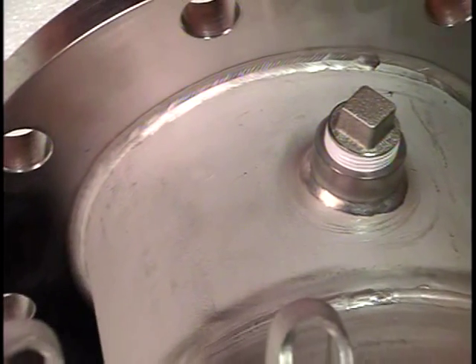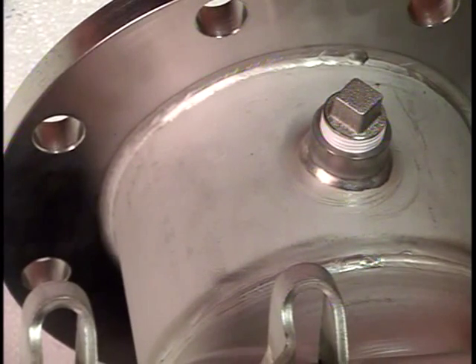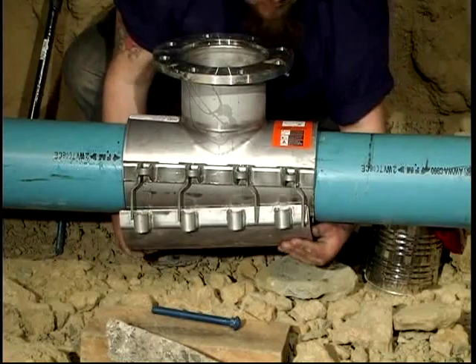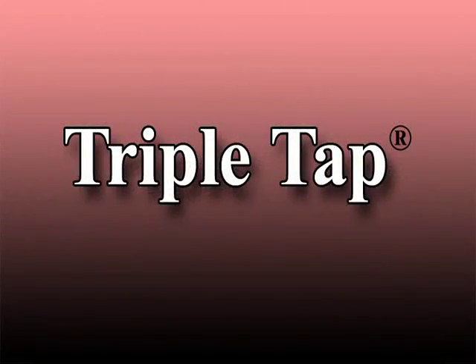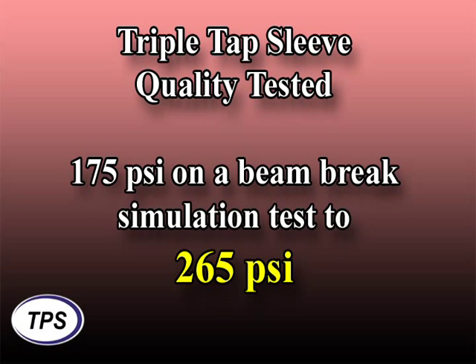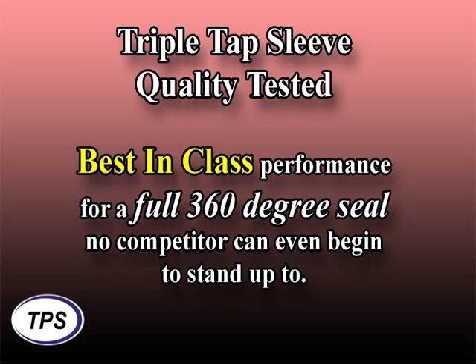This patented design provides fatigue-resistant, 100-percent penetration branch welds. It utilizes an extra heavy-duty shell and lug system. Every Triple Tap Tapping Sleeve is qualification tested to 175 PSI working pressure on a beam-break simulation test to 265 PSI. For stainless steel fabricated tapping sleeves, this equates to best-in-class performance for a full 360-degree seal no competitor can even begin to stand up to.